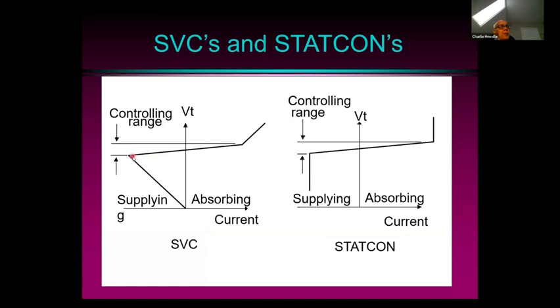But if it still persists in going down, at some stage, you reach the limit of your shunt capacitance. When you reach this limit, then if the voltage wants to go down even more, the power delivered by the shunt capacitance starts to get less very quickly because it's proportional to V squared. So the shunt capacitance is not as good as the alternative, which could be a static VAR compensator, which has the same shape of characteristic in the control range, but when it reaches its limit, it's only limited by the amount of current it can produce, so it just goes straight down instead of going down as fast as the shunt capacitance. So these are some techniques that have been used to mitigate the problem of declining voltages as the system approaches its limit of available reactive power.